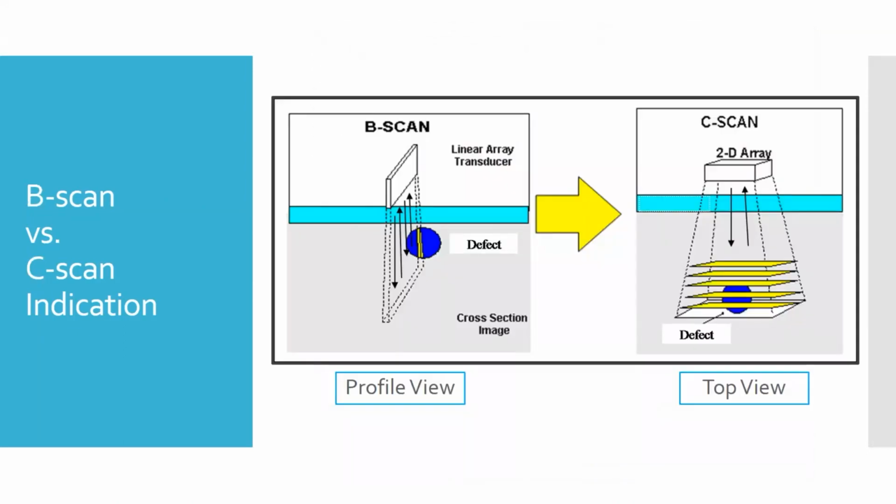The next type is, so B-scan is shown here, and this shows a B-scan with other things. A B-scan is basically a line. What they're showing on this B-scan is that a transducer was run from the bottom left to the top right. As it's going along, it sends pulses. It does a pulse here, a pulse here, a pulse here, as it moves across.